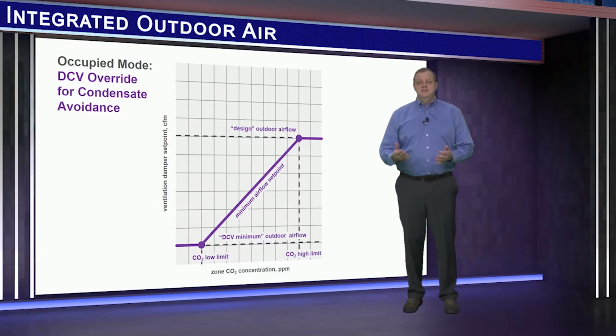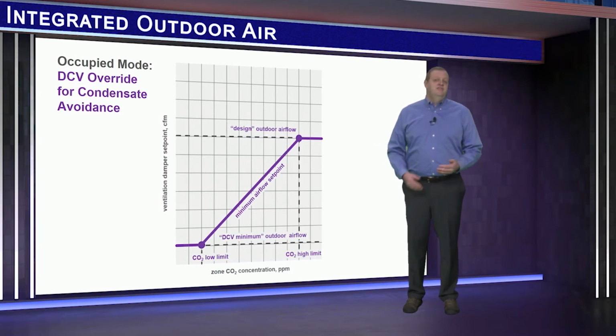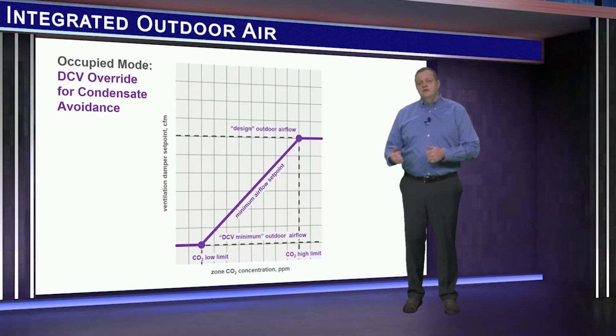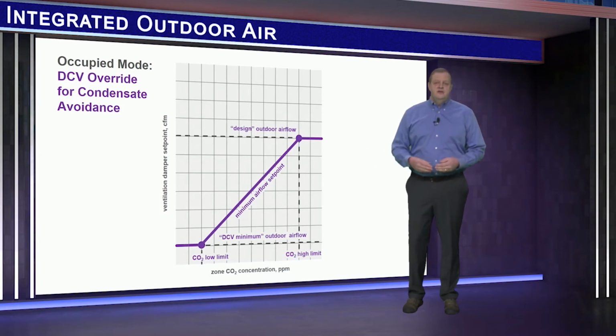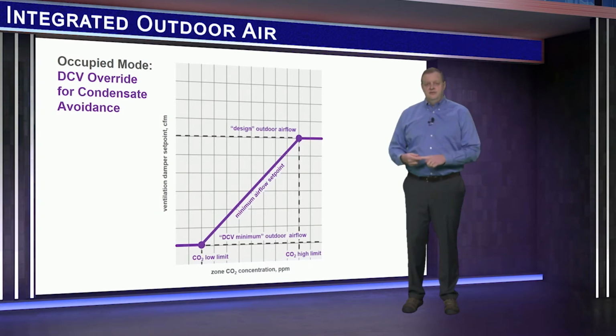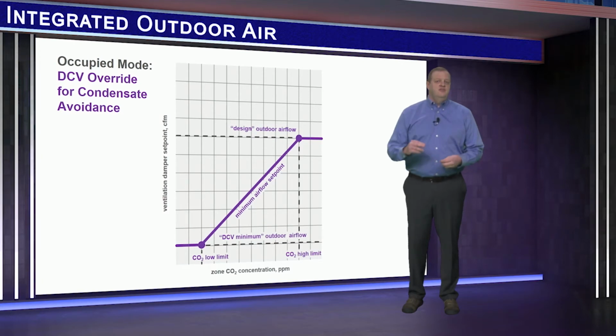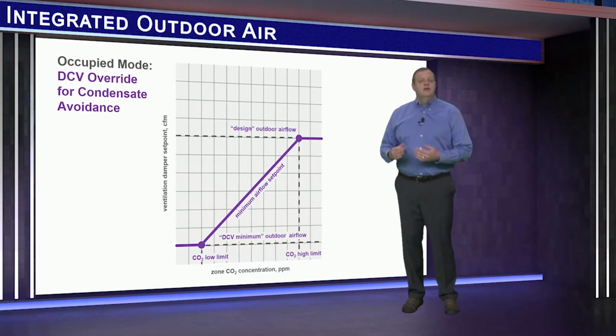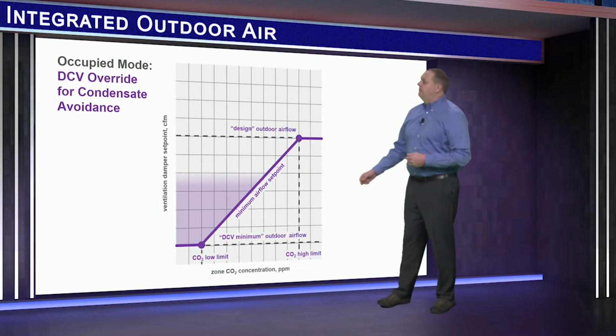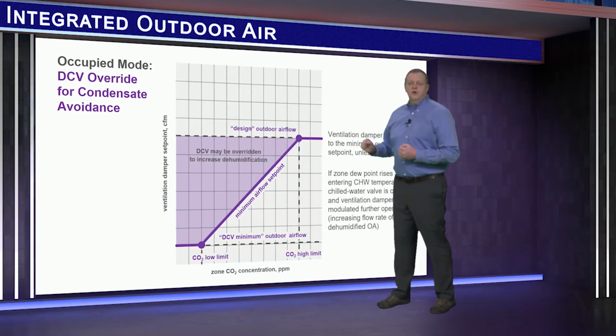Now, if the only latent load is due to people, that's probably not an issue. If the people are not there to generate CO2, they're also not generating humidity. Even so, the Trane controller contains logic that will override this demand control ventilation if additional dehumidification is required. So if you install a humidity sensor in the zone, it's used to calculate the current zone dew point. If that dew point rises above the entering water temperature, the controller will temporarily close the chill water valve and modulate this ventilation air damper further open.